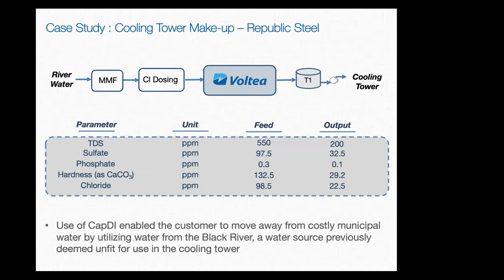Again, an example here we have is Republic Steel, which is a steel mill up in Ohio. They were burdened with high cost water from the municipality for the use in their cooling tower. They wanted to look for an alternative, which was right on their doorstep in the case of the Black River. The issue with that is, maybe from the name as it's implied, it's not very high quality water.